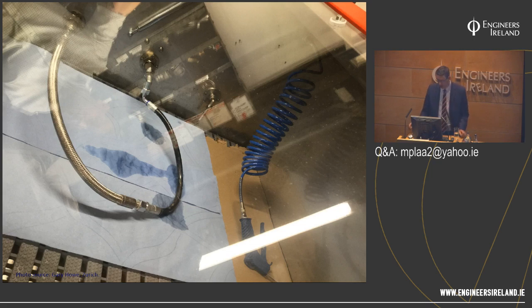Now, this is an interesting case, this one. This one resulted in a very large insurable claim in a very expensive block of apartments in London, where a water mist system activated due to a fire. But what happened is the contractor, rather than using the listed certified manufacturer specified flexible connection, decided to buy their own version because they were cheaper.